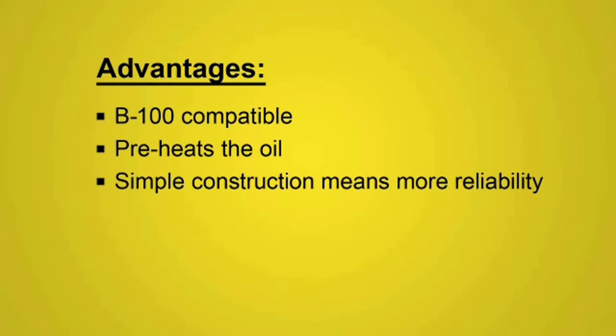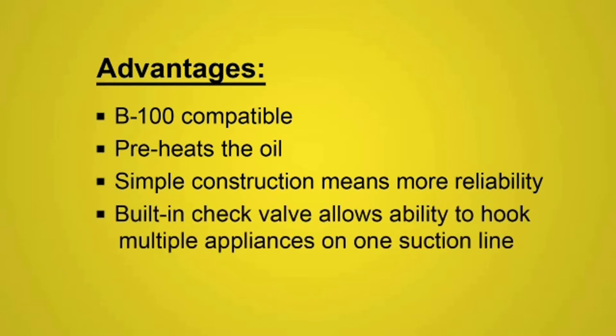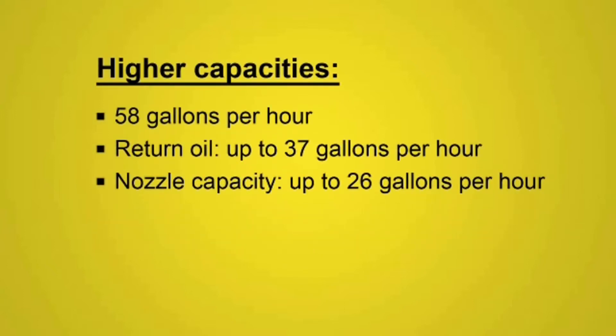This deaerator has simple construction, meaning more reliability. No diaphragms, just a simple throttling valve on the bottom. A built-in check valve allows the ability to hook multiple appliances on one suction line, using a single deaerator per appliance, without worry of one appliance pulling the oil from the other. This design allows for higher capacities, with a maximum capacity of 58 gallons per hour. This is a combination of return oil and nozzle capacity.